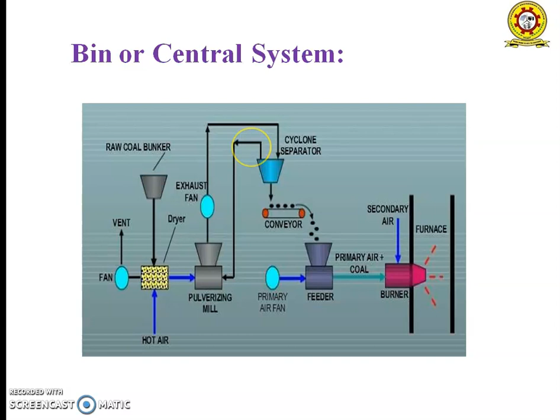The pulverized coal obtained is transferred to the pulverized coal burner through the cyclone separator, which we are using here. The transportation air is separated from the coal by a cyclone separator. The primary air is mixed with the coal at the feeder and the mixture is supplied to the burner.